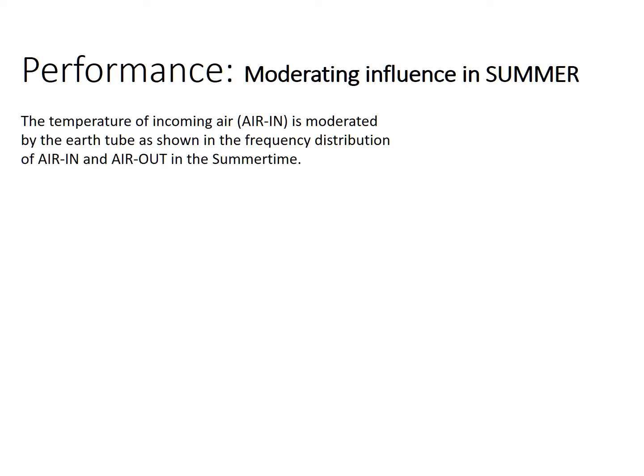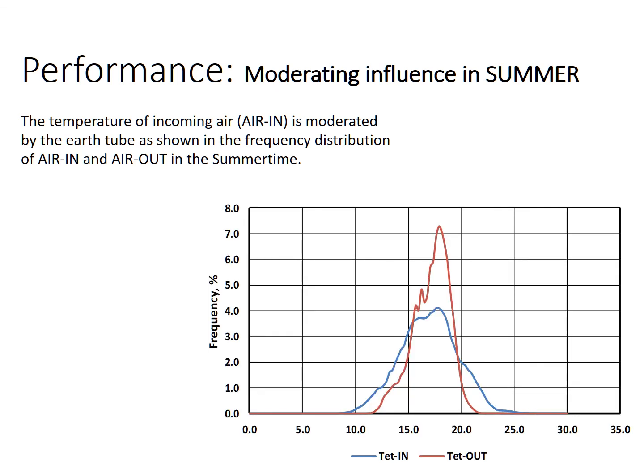And one of the big things about the earth tube, it moderates the incoming air, of course. Temperature of the incoming air is moderated by the earth tube, as shown in the frequency distribution of air in and air out, just looking at the summertime of June, July, August. So we have the frequency distribution, our frequency on the y-axis, and we have the air temperature on the x-axis. The blue line shows the distribution of air coming into the earth tube, and the red line for the air exiting the earth tube. And you can see this is constricted. The outgoing air has a lesser range than the incoming air, significantly 2 or 3 degrees on either side. So this is very helpful. The earth tube acts as external thermal mass in effect.